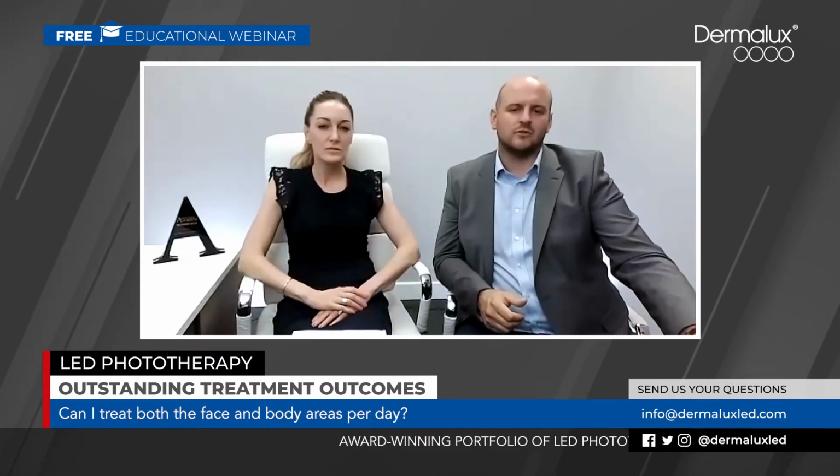The rules around LED treatments: when a manufacturer generates an LED product, we have to produce what's known as a clinical evaluation report, or CER. In this, we have to provide all our clinical studies and evaluations of how clients have reacted to the light, and whether we've seen any evidence that skin conditions have improved. That data gets audited by your notified body and the likes of the MHRA, who approve it to state that a device is capable of relieving or treating a particular medical condition.